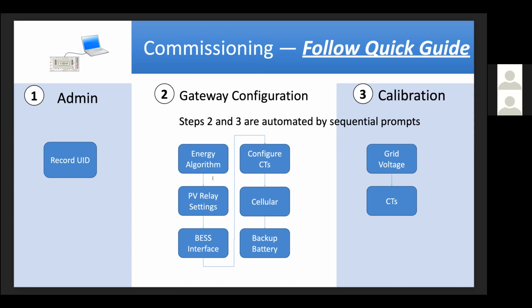Then you would go into the configuration steps and follow the quick guide and put in whether it's self-supply, time of use, etc. Configure the CTs. There's an auto detect feature that's really nice. It'll walk you through automatically detecting all of the CTs in the system, and based on that logic, will tell you if you've made any errors on placing the CTs, wiring the CTs, or if your phase wiring on your AC conductors has been reversed anywhere from the main service panel to where those CTs are, whether it's in the backup loads panel for the PV or the battery itself.